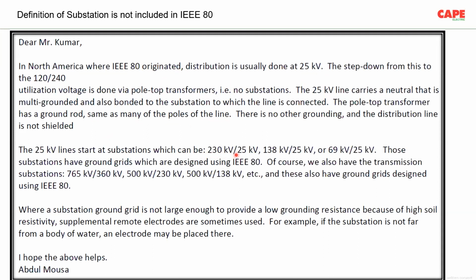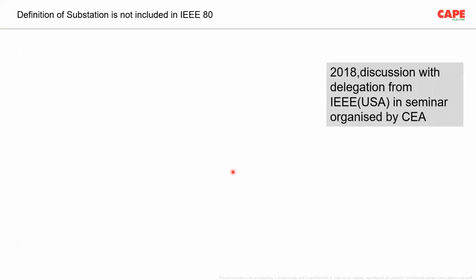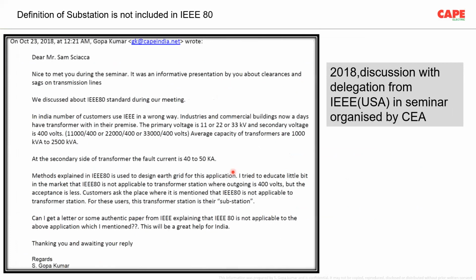It is used for 230/25 kV or 138/25 kV, or you see, these are the extra high voltage substations. That is the place where IEEE 80 is really used in America. But the problem in IEEE 80 is that nowhere is the applicable voltage written. The definition of substation is missing in IEEE 80. About 2 years back, an IEEE delegation came to Delhi. There was a common seminar. I made a presentation to all the participants.